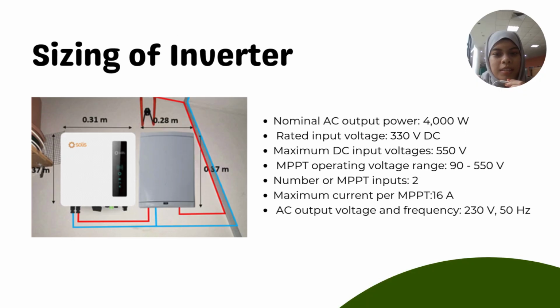So next is the sizing of the inverter. The nominal AC output power is 4000 watt. The rated input voltage is 330 volt DC. The maximum DC input voltage is 550 volt. MPPT operating voltage range is between 90 to 550 volt. The number of MPP inputs is 2. The maximum current per MPPT is 16 ampere. And the last one is the AC output voltage and frequency, which is 230 volt and 50 hertz.